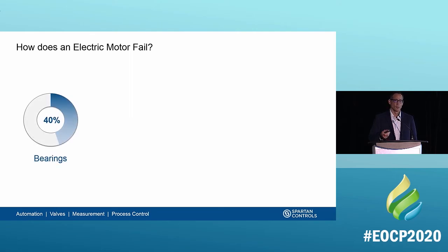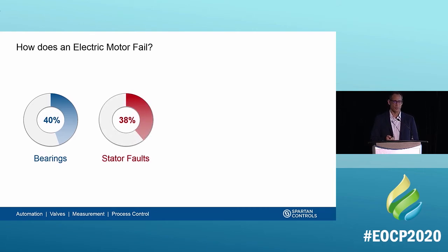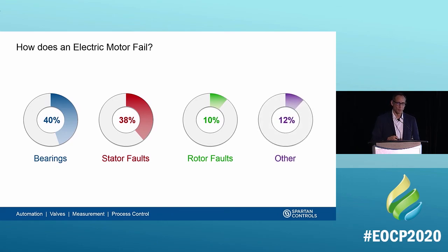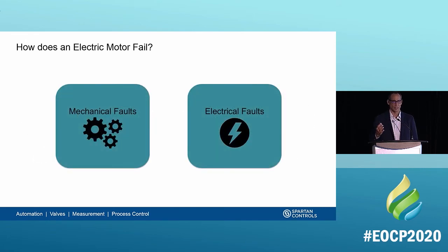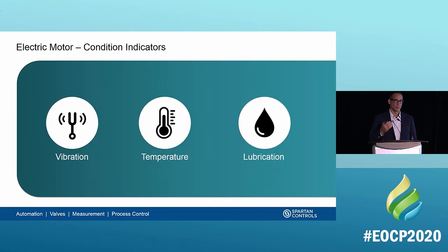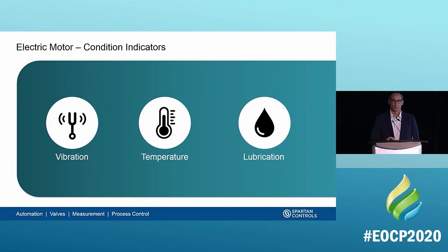How can a motor fail? Statistics show that about 40% of electric motor failures are due to bearings, which maintain the rotor on its axis as it spins. About 38% are stator faults, 10% are rotor faults, and about 12% are other causes. We can group these fault conditions into two categories: mechanical faults and electrical faults. The key indicators of these fault conditions include vibration, temperature, and lubrication. We're going to focus on vibration specifically since there isn't time today to cover the other two.